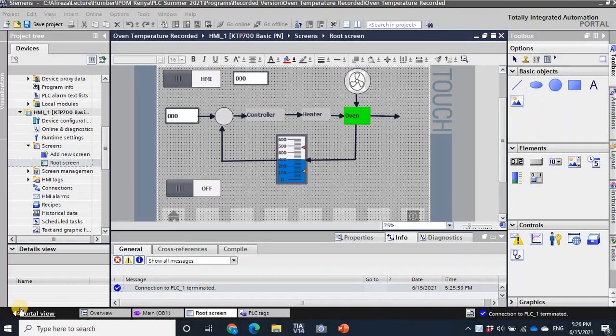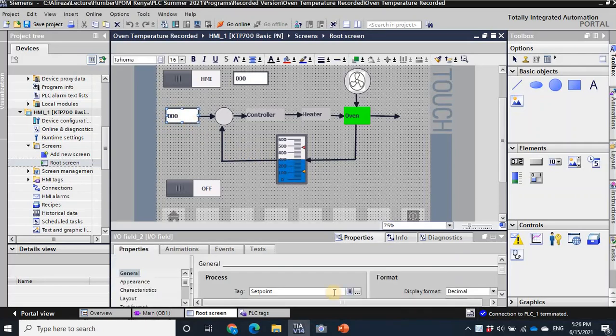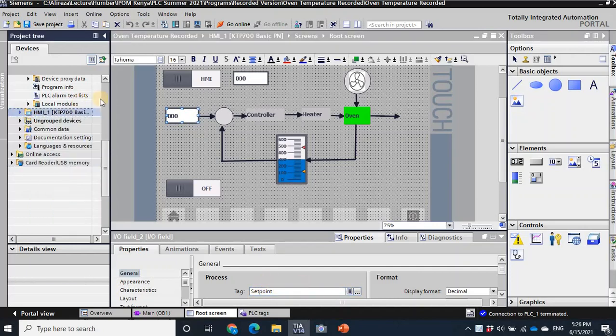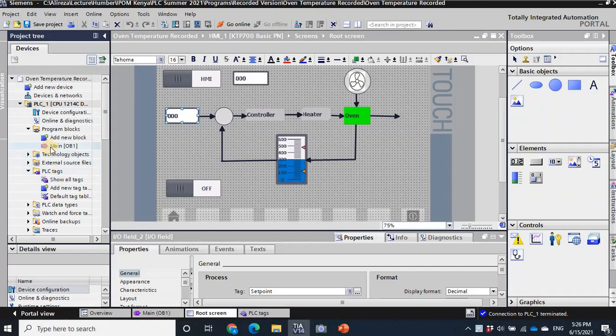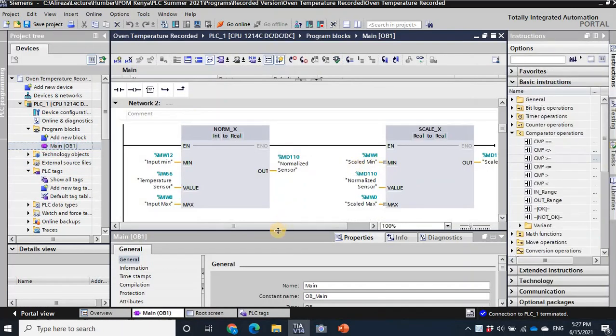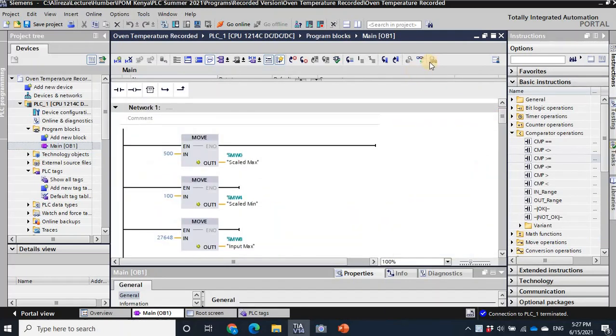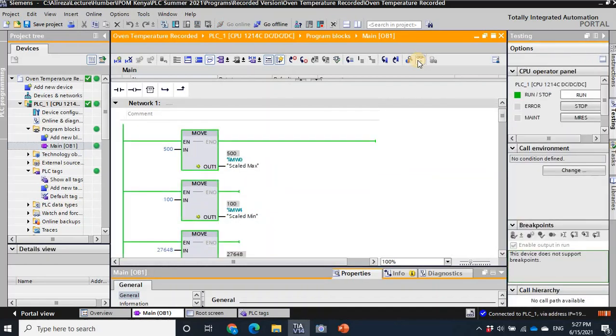This is continuing as a second part. The problem was that when we change the set point it doesn't change, but then the temperature changes. There was some mistake — it's not because of the HMI, so there should be something wrong in the PLC. To find out what the problem is, let's set the PLC to online monitor mode so we can see the values.